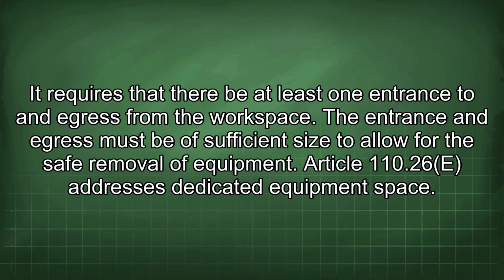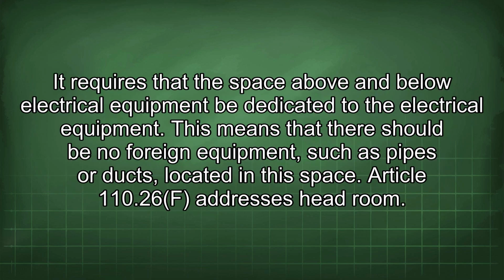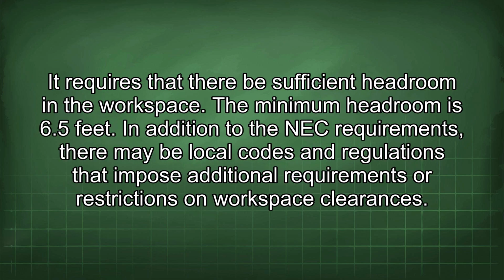Article 110.26(E) addresses dedicated equipment space. It requires that the space above and below electrical equipment be dedicated to the electrical equipment. This means that there should be no foreign equipment, such as pipes or ducts, located in this space. Article 110.26f addresses headroom. It requires that there be sufficient headroom in the workspace. The minimum headroom is 6.5 feet.